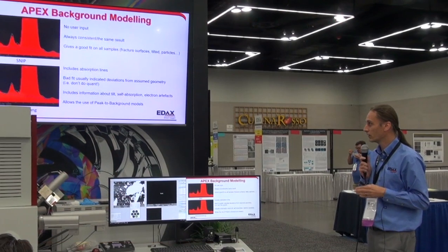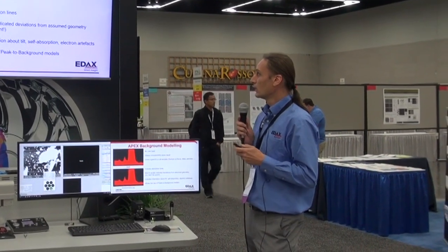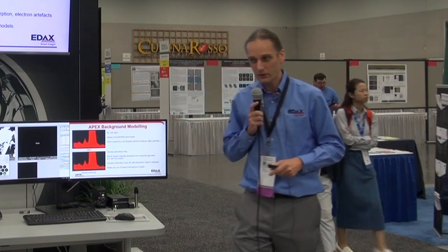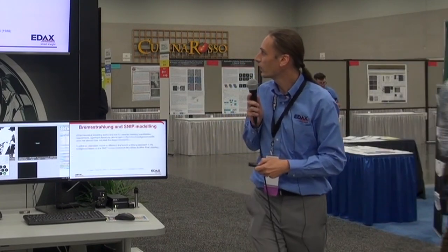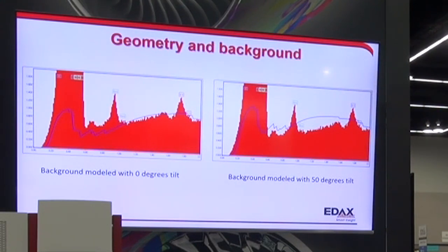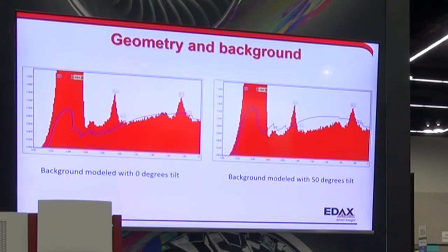The Bremsstrahlung is generally my recommendation. If you're doing quantification, there's a lot of useful information hidden in the Bremsstrahlung model. But if you're doing qualitative analysis — just figuring out what elements are in there — and you're looking at a fracture surface, particulates, or whatever, you can get a bad fit. You'll get something like what we have here where you have a misfit — the background is higher than the signal — and if you're trying to figure out whether you have a peak there, you're cutting off over half the counts. The SNIP model would just model the background in that case, making it easier to identify peaks.